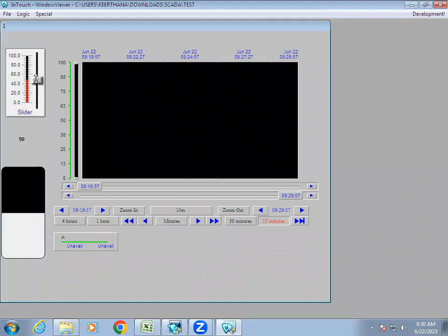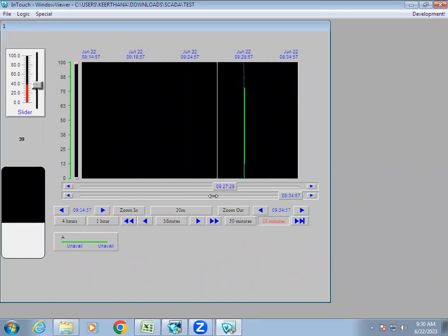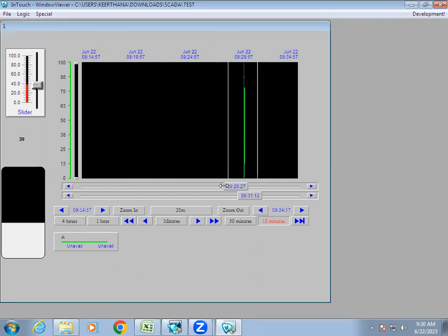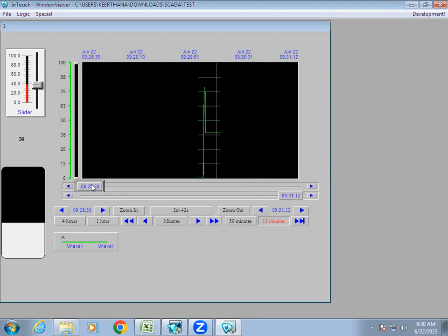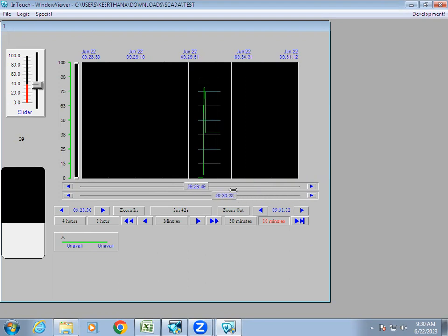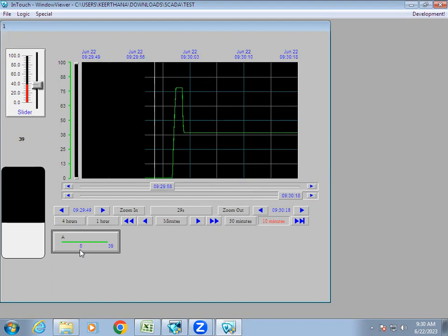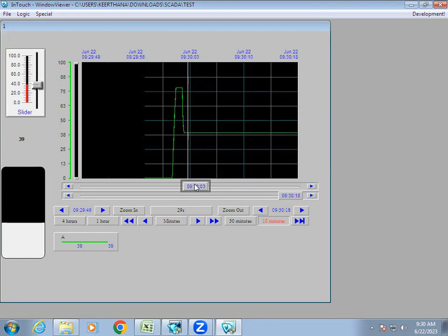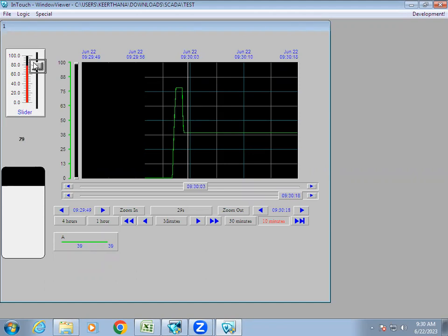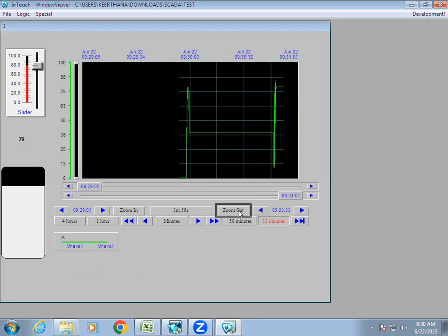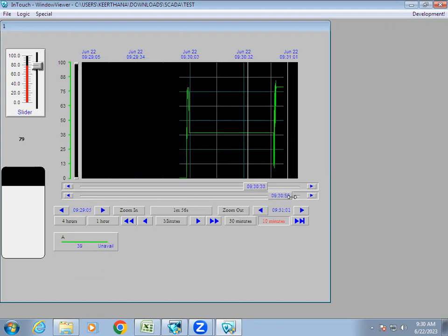At runtime, make some value changes, then click Zoom Out — you can see the scale on the chart. You can select the time range you want to see and then Zoom In again. When you move the cursor you can see in the pen legend it shows the value at that point in time. Note that after making new changes you need to click Zoom Out each time to refresh and see the updated data. This way you can view past data as well.